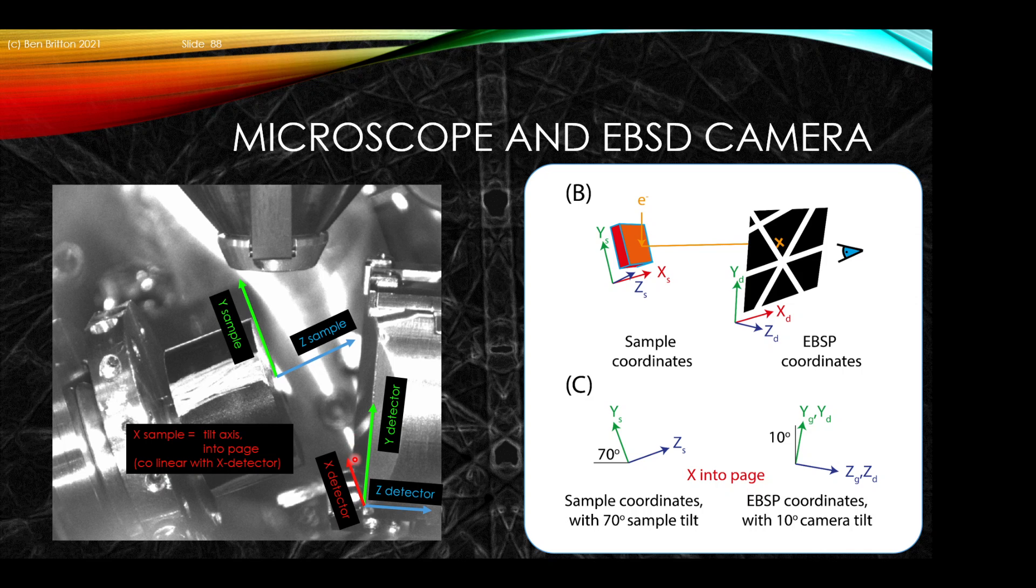We have a tilt axis that tilts us between the detector and the sample, so the X direction for this microscope is common between the sample tilt and the detector tilt. Therefore the Z and Y will rotate about this X vector going into the page, and both form a right-handed set. Conventionally we set up the experiment by tilting the sample to 70 degrees, so there's a 70 degree angle involved. There may also be a tilt of the camera, which we describe as about 10 degree detector tilt in this example.